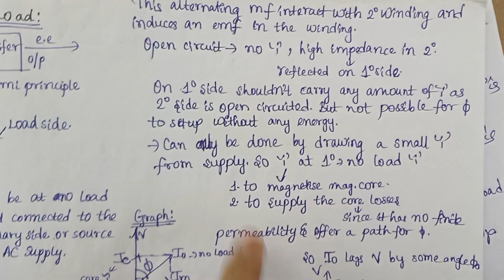So we have to give current at the primary winding. This current is called the no load current, and the main reason for it is to magnetize the magnetic core, and then to supply the core losses.